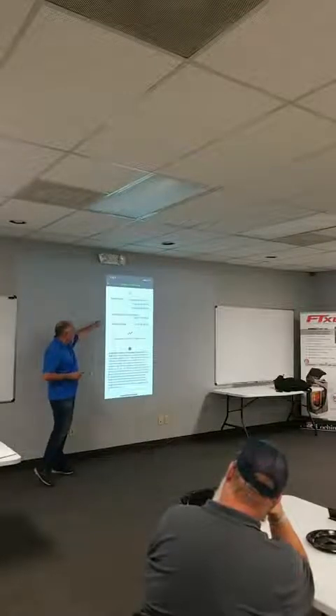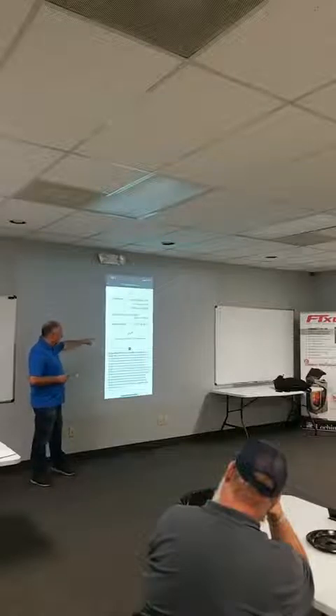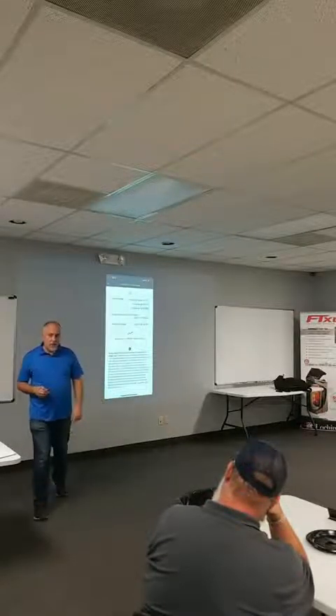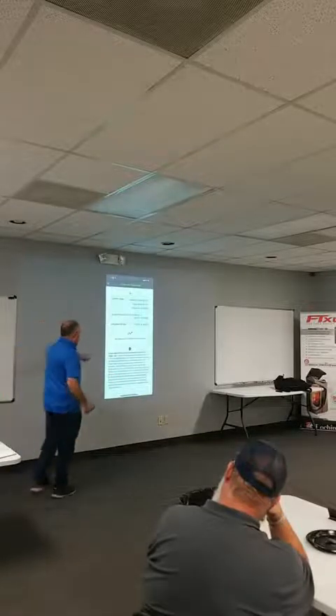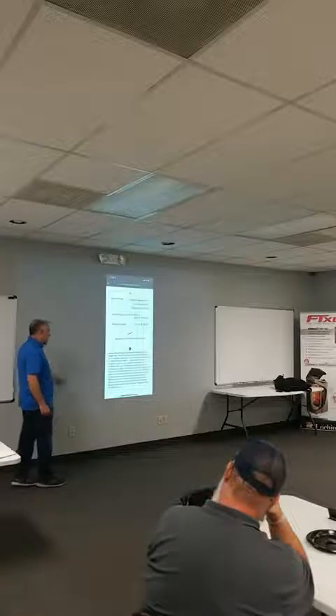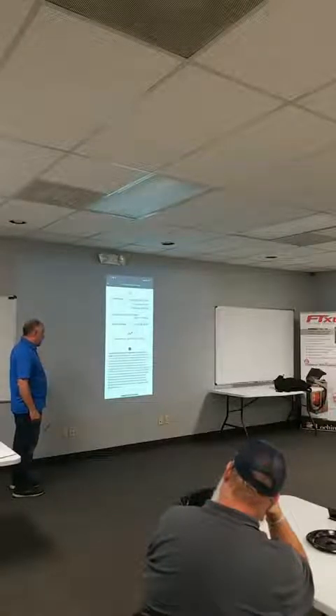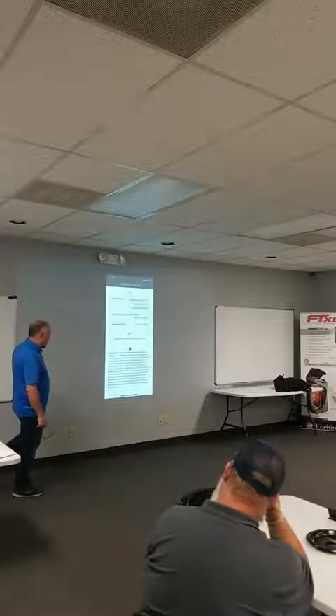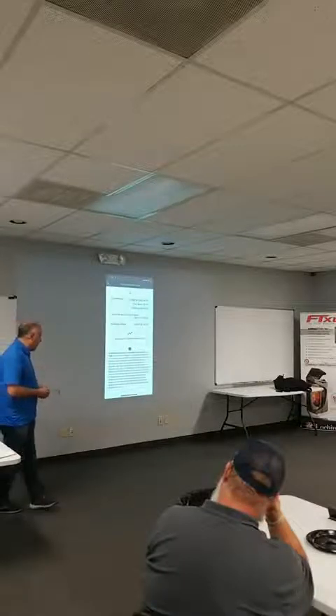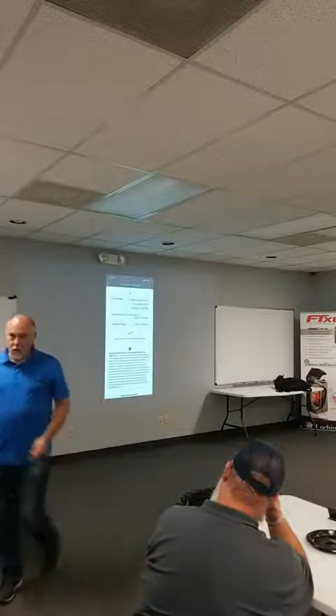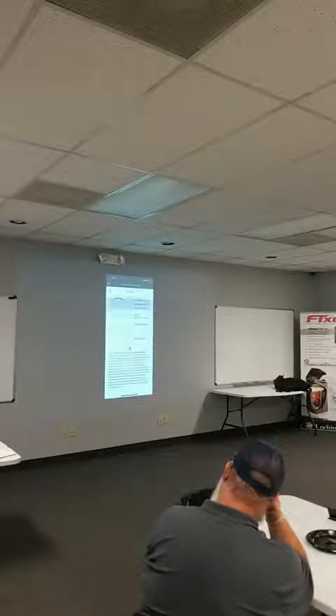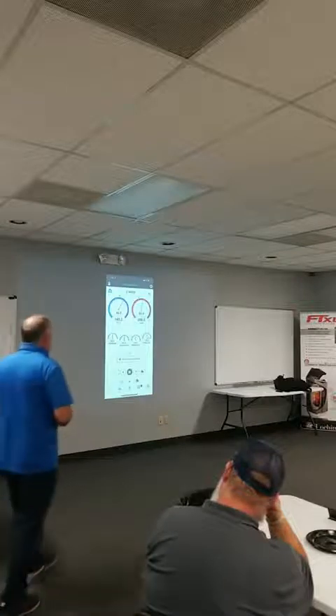So it calculates the design center of the glide, and it calculates the allowable range, and then it shows you with a little arrow if it's above or below the range, and then it tells you down below what to look for. So high suction pressure is normally a singular problem. It's most commonly caused by refrigerant overcharge in combination with high subcooling and low superheat in fixed orifice systems. High suction pressure can also be the result of high load, inadequate airflow, or an overfeeding TXV. It can also occur with a normal flooded evaporator. To adjust refrigerant charge, verify the superheat and subcooling are in range. Verify the airflow, check for matched components, including condenser, evaporator, and metering device. Right, so it walks you through not only what it's supposed to be, but what to look for if it's in the wrong range.